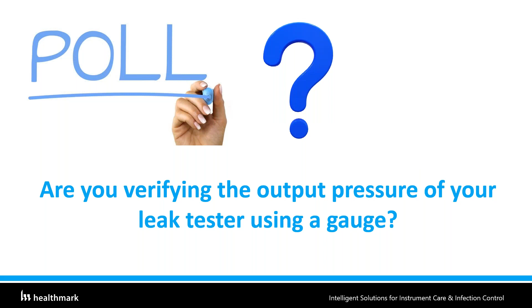Thanks for that. So for the 59% that didn't, this could happen to your scope. This scope actually went for repair, and when they received it, they were looking for some other issue. When they opened it up and took that black shield off, this is what they saw underneath that shield. They didn't know it was leaking, so they didn't send this for repair for a leak. So this is what happens if you have an inadequate leak tester.